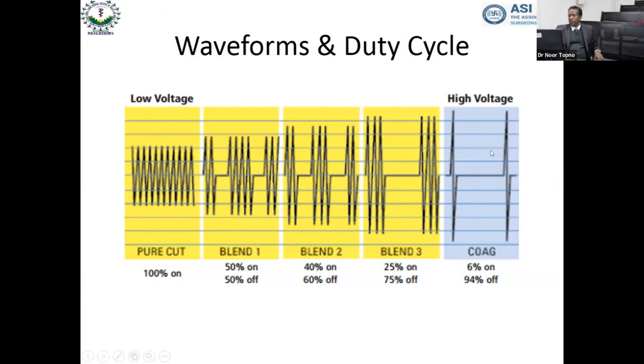So this is basically called the duty cycle. Here, in coagulation mode, the flow of current is not continuous. Only for 6% of the time, current flow is happening. And that is how the heat generated here is different as compared to the pure cut mode. And in between, we have different blends, which is basically a variation of the voltage, whether it is low or on the higher side, and also how long the current is flowing.